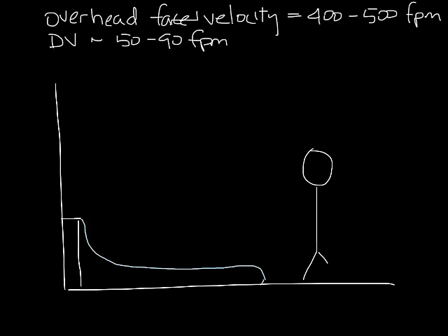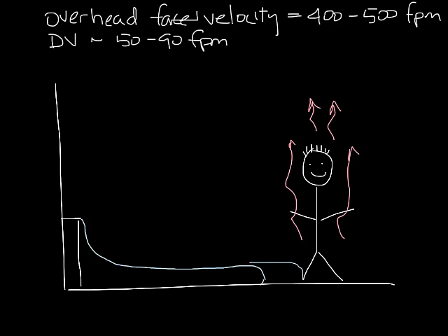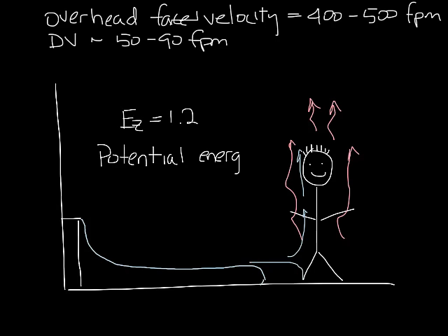When the supply air comes in contact with a heat source, also known as a person or maybe a computer, the heat will cause the air to rise, and this convection plume lifts contaminants up and out of the occupied zone. This also pulls supply air up across the person, providing them with comfort and fresh air. For this reason, ASHRAE gives displacement ventilation systems a ventilation effectiveness of 1.2, meaning you can reduce the amount of fresh air that you have to bring into the space. This can result in energy savings as well.